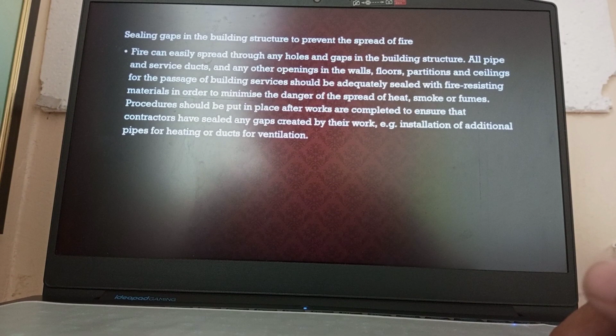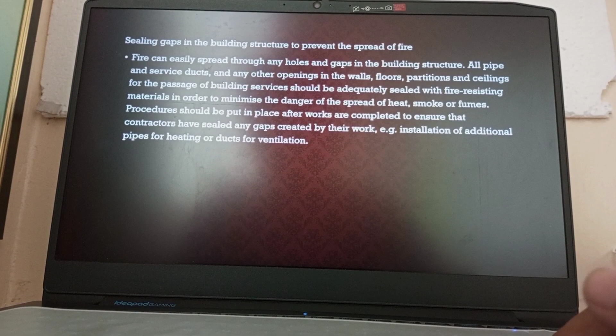Sealing gaps in the building structure to prevent the spread of fire. Fire can easily spread through any holes or gaps in the building structure. All pipe and service ducts and any other openings in the walls, floors, partitions, and ceilings for the passage of building services should be adequately sealed with fire-stopping materials in order to minimize the spread of heat, smoke, and fumes. Procedures should be put in place after works are completed to ensure that contractors have sealed any gaps created by their work.